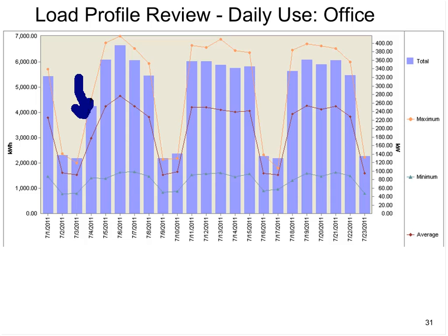One other thing I'd like to call your attention to is the demand, which you'll see your orange maximum demand, and the maroon is the median or the average, and then your minimum is the green. Now, the one you'd be concerned about is the orange, and you'll see over here that kW reached about 420. That is the value you'd see on your bill. So if there's any way you can shave demand, you'd start looking there. What are your demand values? What consistently are they at? And basically know what to expect. So, like I said, just some more good examples.